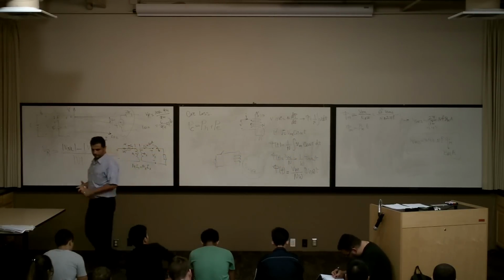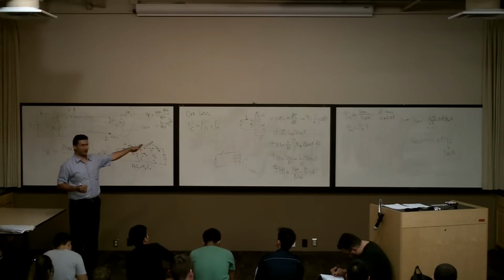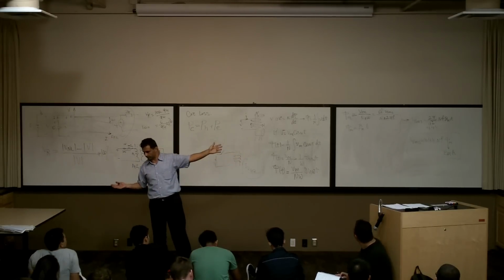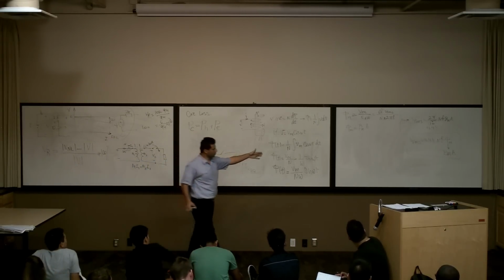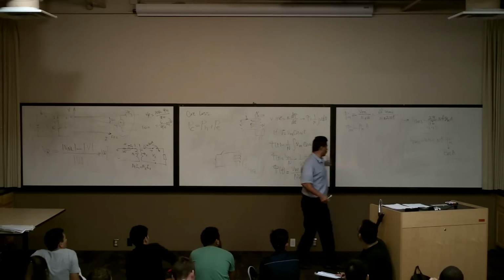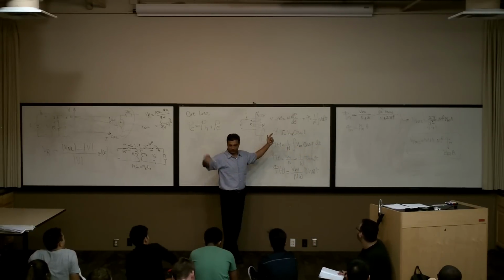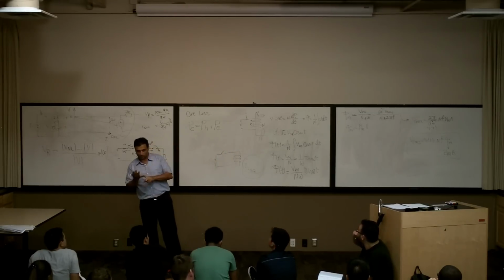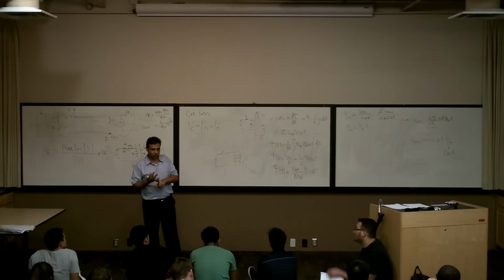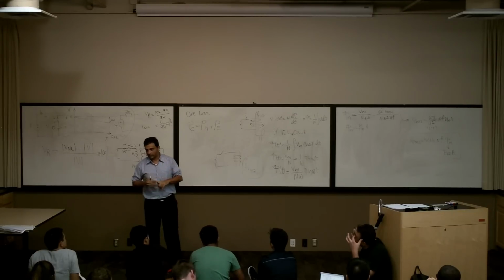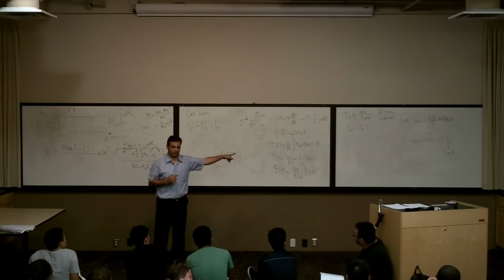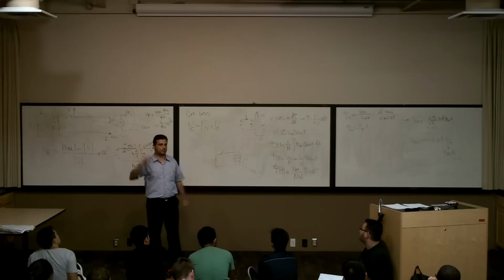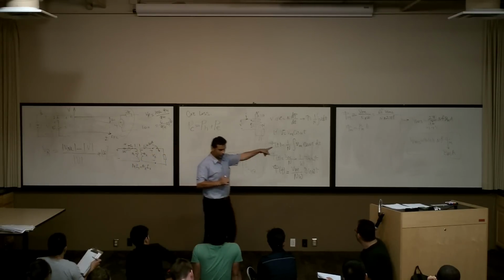If you have a sine wave, you know how many turns you have, you know the frequency of the voltage, 50 hertz, 60 hertz, whatever it is. It's all known. You know the cross section of the core, for example, a donut core. If you know the cross section, the number of turns, and the frequency you are using, you can calculate B maximum. If I connect 100 volts here at 50 hertz, how much is B maximum for this core? You can use this equation.